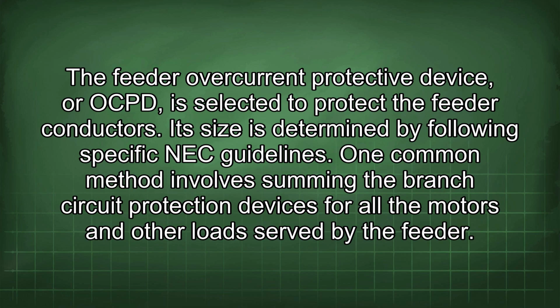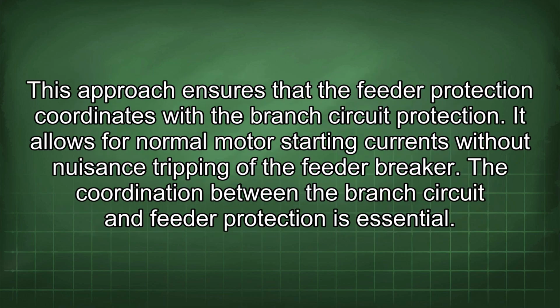The feeder overcurrent protective device, or OCPD, is selected to protect the feeder conductors. Its size is determined by following specific NEC guidelines. One common method involves summing the branch circuit protection devices for all the motors and other loads served by the feeder. This approach ensures that the feeder protection coordinates with the branch circuit protection. It allows for normal motor starting currents without nuisance tripping of the feeder breaker.